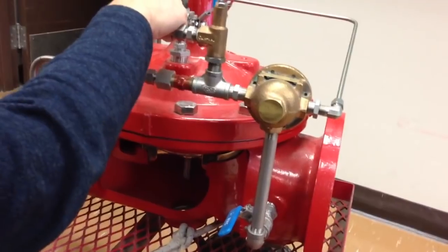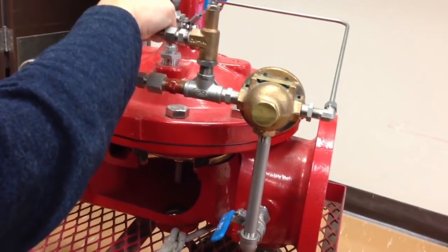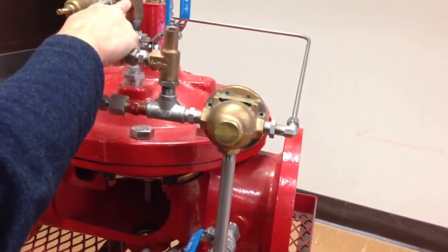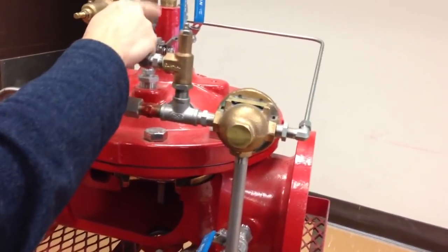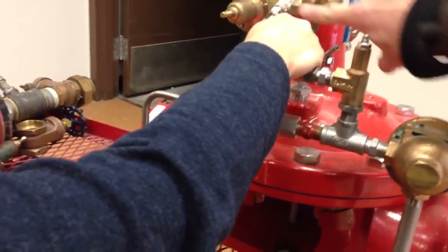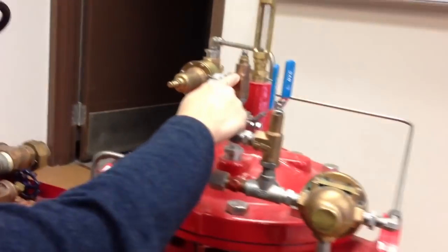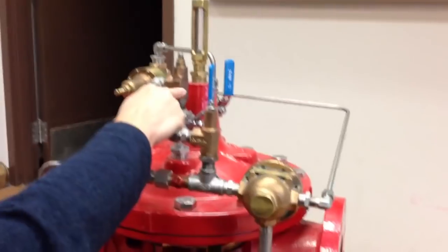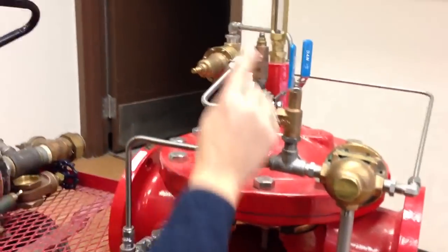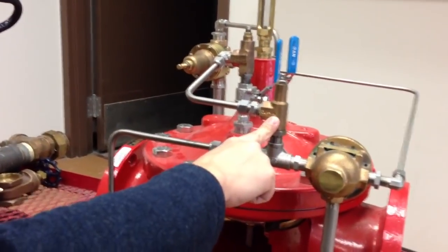It isn't until here where the water has to pass through the constriction and then go down here. So this one actually controls how fast this water comes onto the top of this valve. So it's restricted this way, not restricted this way. This one will control how quickly water goes on top of the valve, but this one controls how quickly water comes off the valve.